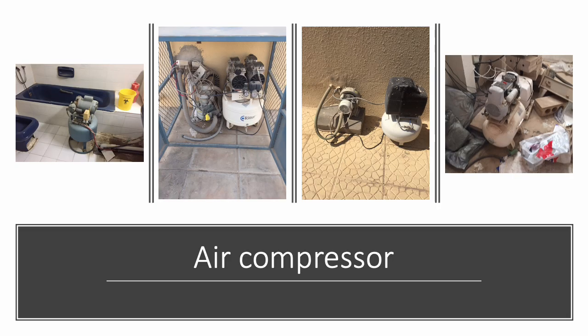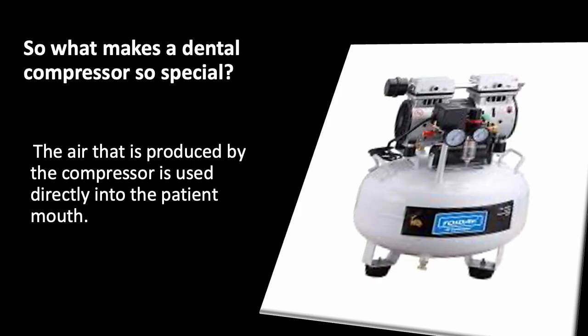Air compressor. So, what makes a dental compressor so special? The air that is produced by the compressor is used directly in the patient's mouth. The patient will inhale the air and swallow any contamination that is within the compressed air.